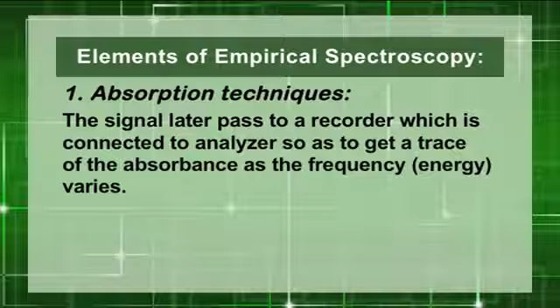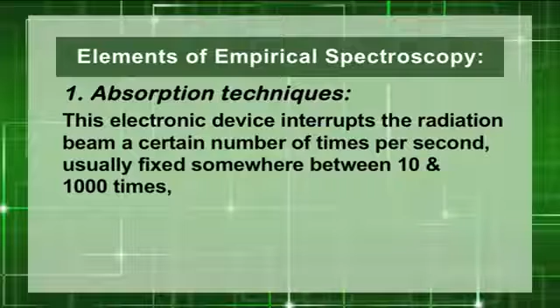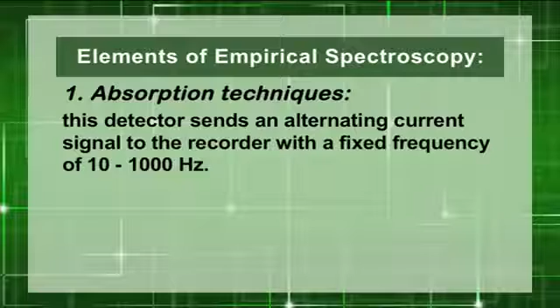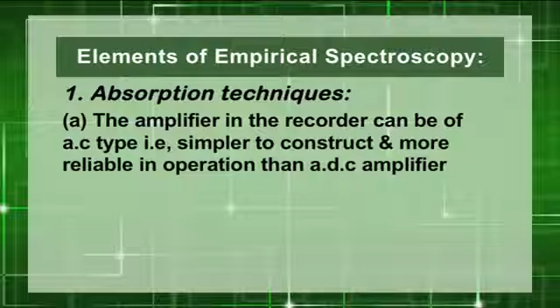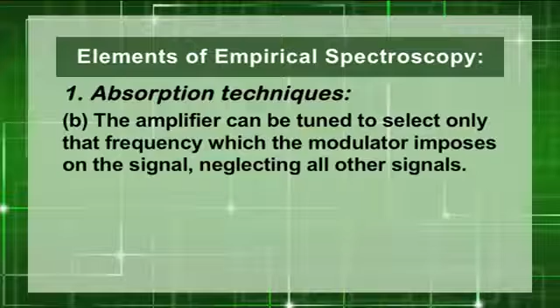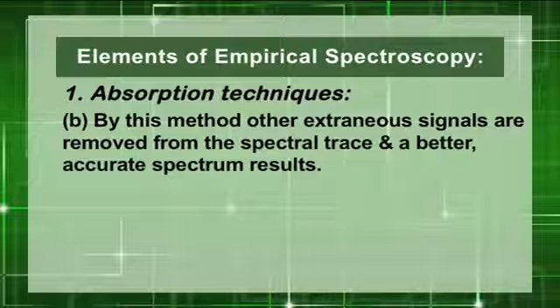This electronic device interrupts the radiation beam a certain number of times per second, usually fixed somewhere between 10 and 1000 times, and the detector sends an alternating current signal to the recorder with a fixed frequency of 10 to 1000 Hz. The two main advantages of this technique are the amplifier in the recorder can be of AC type, that is simpler to construct and more reliable in operation than a DC amplifier, and the amplifier can be tuned to select only that frequency which the modulator imposes on the signal, neglecting all other signals. By this method, other extraneous signals are removed from the spectral trace and a more accurate spectrum results.